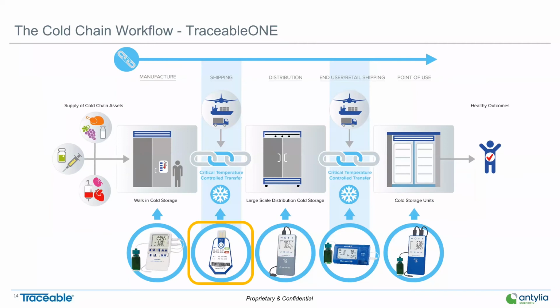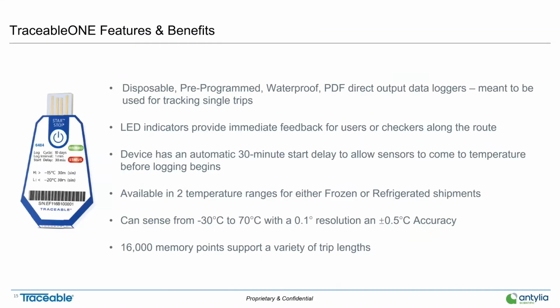So on to the next stop in our workflow, the TraceableOne. So the TraceableOne is Traceable's disposable, pre-programmed, waterproof PDF direct output data logger. We see these primarily used to track shipments, especially distributed shipments, where you need to ensure that the temperatures within that shipment have been maintained at the proper levels. Primarily, these are positioned to be checked at the end of every shipment. They support LED indicators that will let you know if the temperatures have gone out of the pre-programmed ranges.